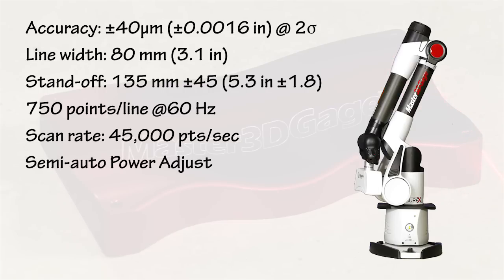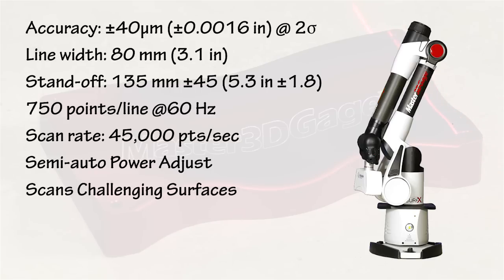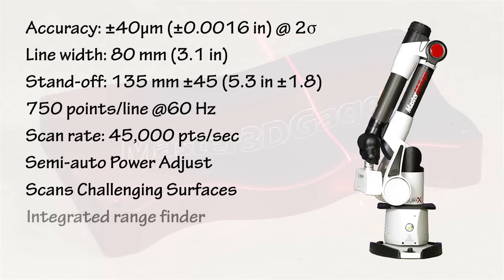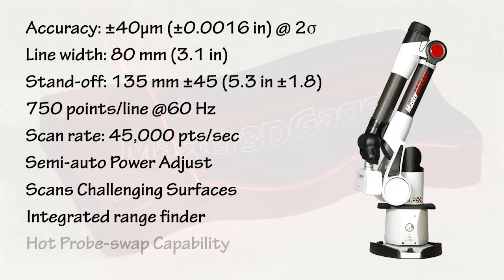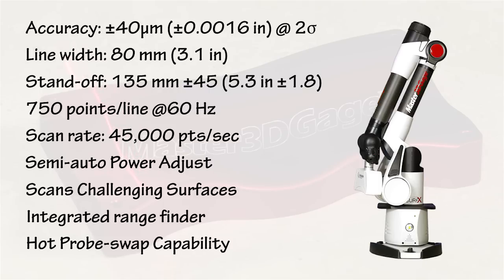Laser power adjustment is semi-automatic, and the laser scans even challenging surfaces like aluminum and carbon fiber. The integrated rangefinder changes color to let you know when the scanner is the correct distance from the part. Finally, the probe mount enables hot-swapping between hard probe and scanner with automatic recognition without having to calibrate.